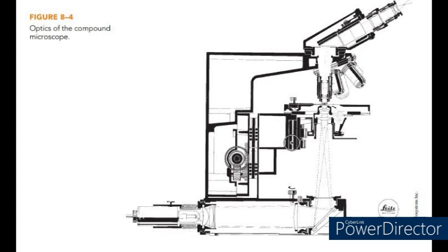Part 1, illuminator. Most modern microscopes use artificial light supplied by a light bulb to illuminate the specimen being examined. If the specimen is transparent, the light is directed up towards and through the specimen stage from an illuminator built into the base of the microscope. This is known as transmitted illumination. When the object is opaque, that is, not transparent, the light source must be placed above the specimen so that it can reflect off the specimen surface and into the lens system of the microscope. This type of illumination is known as vertical or reflected illumination.